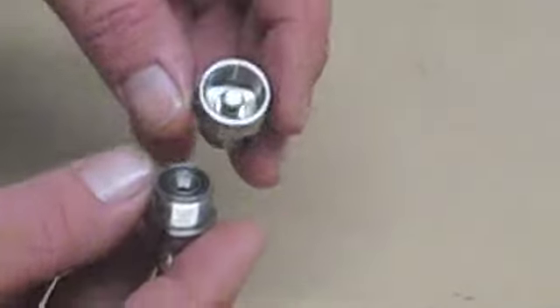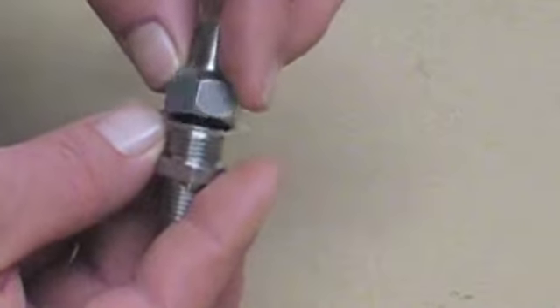Here is the important part. Take the poppet and dump it into the seat. The reasoning is, if you turn it the other way, the O-ring on the seat can fall down and cut the O-ring, which will lead to your pump losing prime and you would have to replace the O-ring.